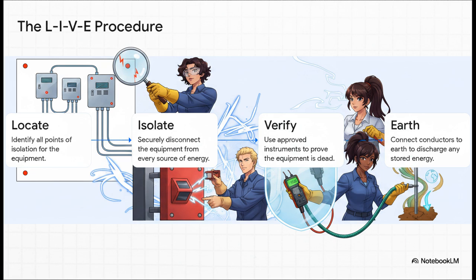LIVE. First, locate. You have to identify every single possible source of power, including any backups. Miss just one, and the whole thing is pointless. Next, isolate. You securely disconnect it and lock it out. Then, verify. This is the moment of truth. You use a meter to prove, not assume, but prove that the circuit is dead. And finally, earth, to drain away any hidden stored energy.